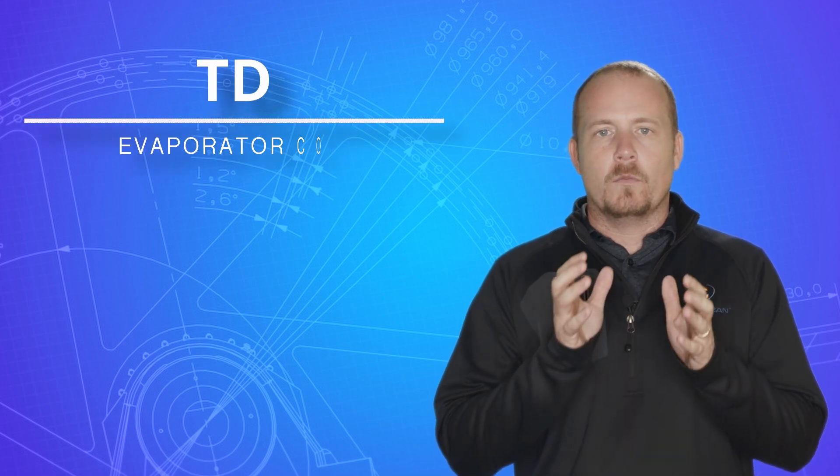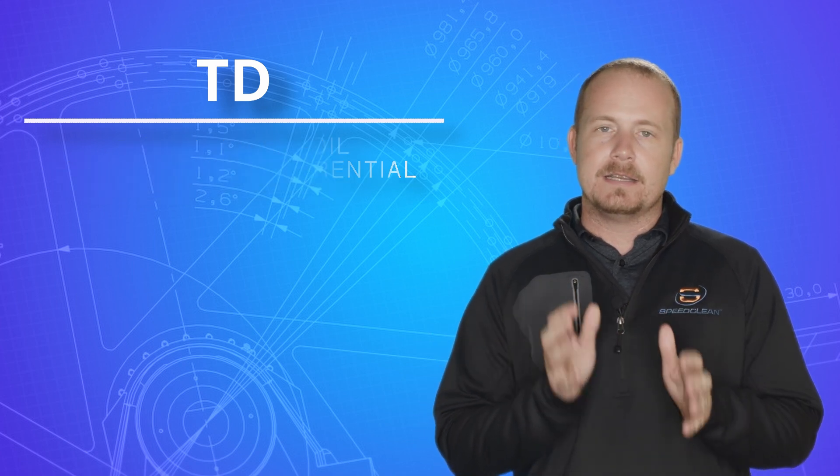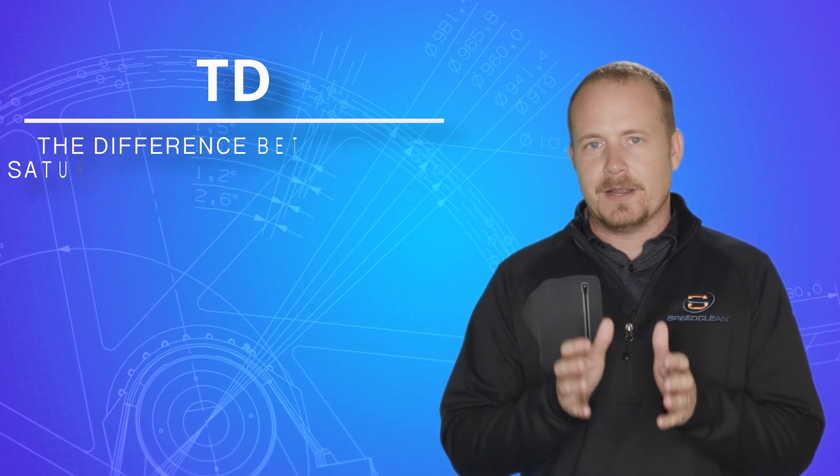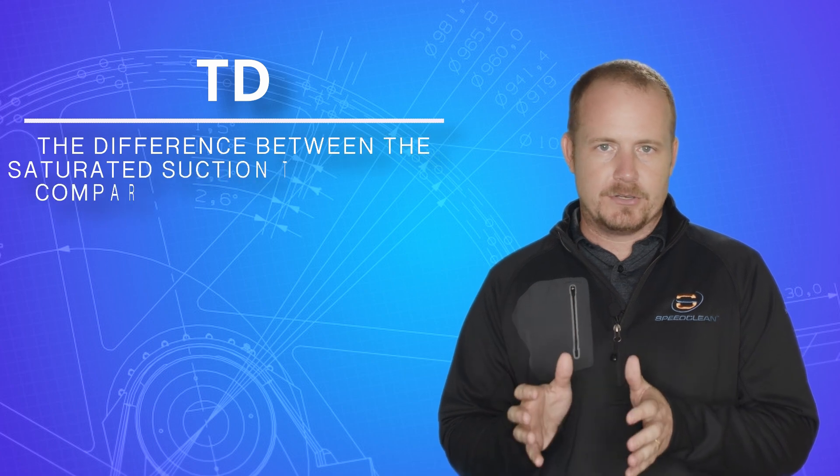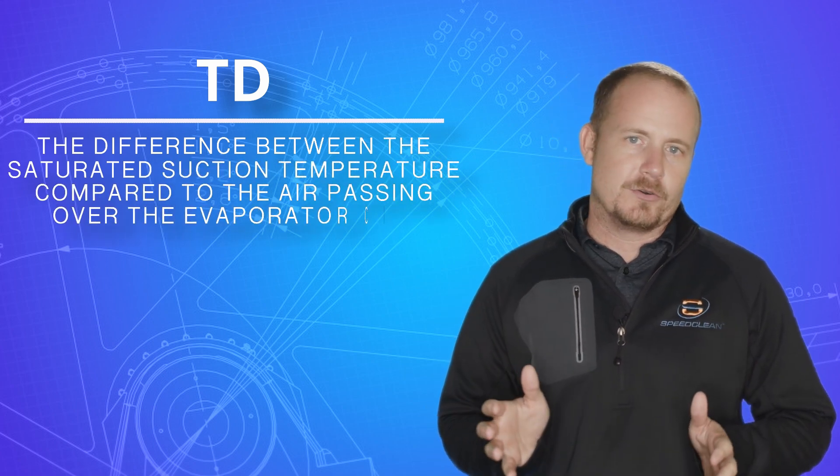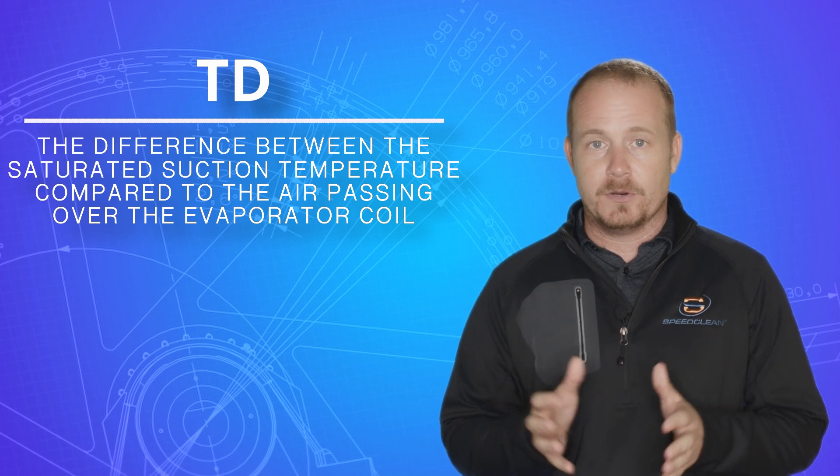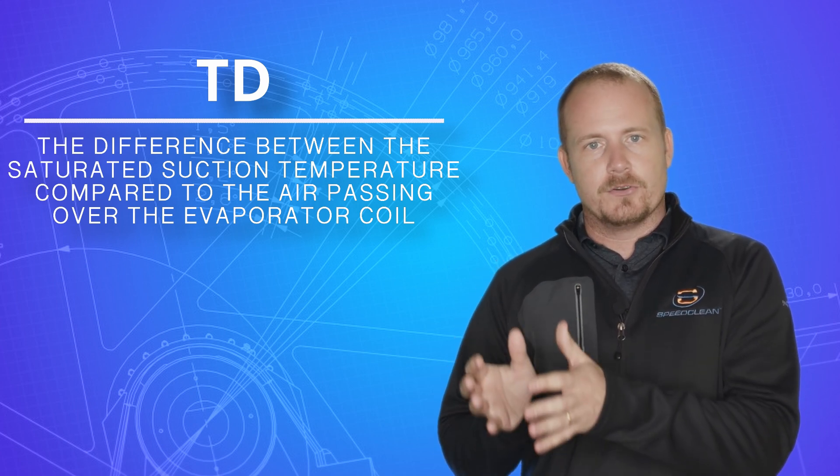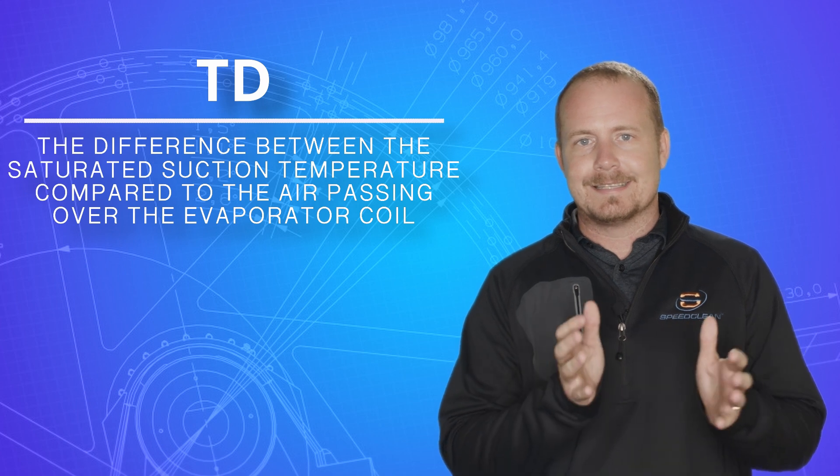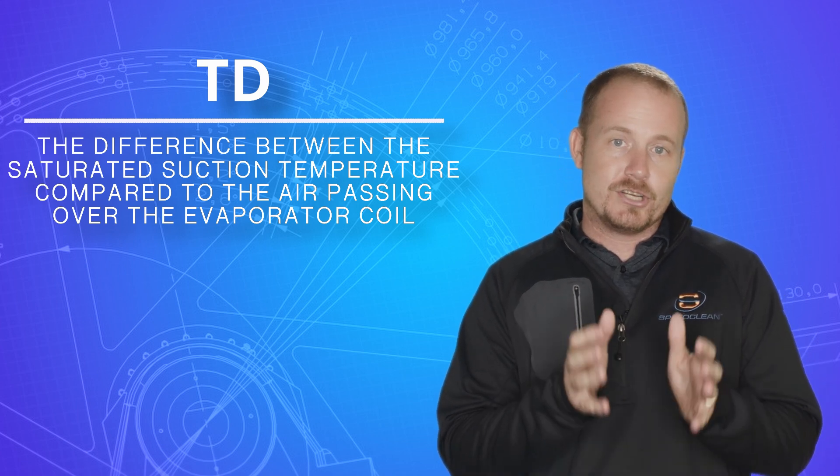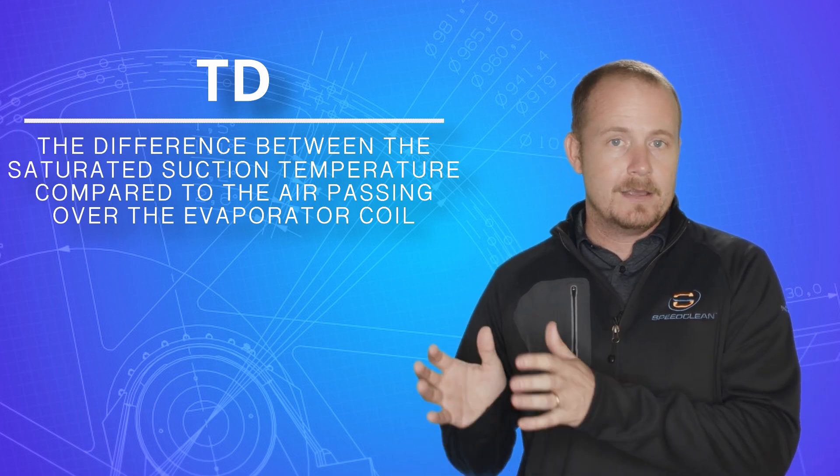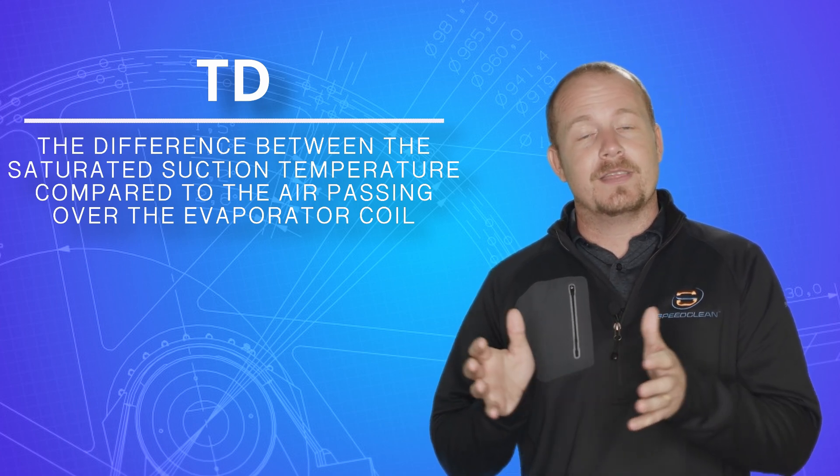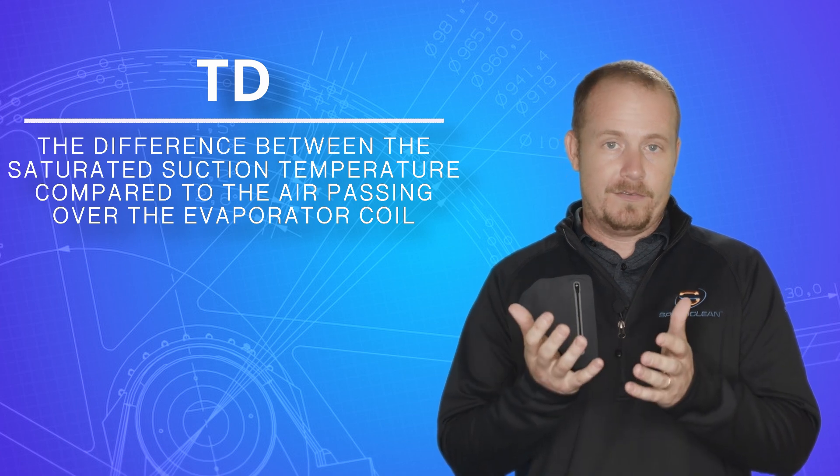When we say Td, we're often talking about an evaporator coil Td. And that means the difference between the saturated suction temperature, otherwise called suction saturation or evaporator temperature, which is specifically the temperature that the refrigerant is boiling inside the evaporator coil, the temperature that is changing state inside the evaporator coil, compared to the air that's passing over the evaporator coil.